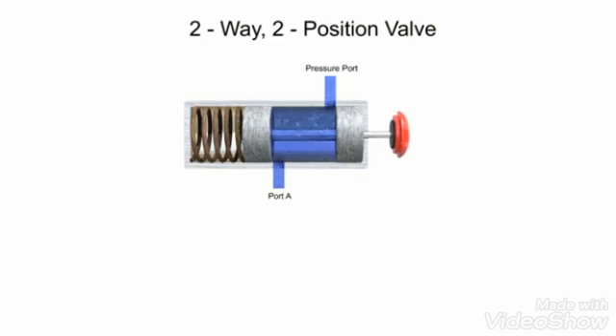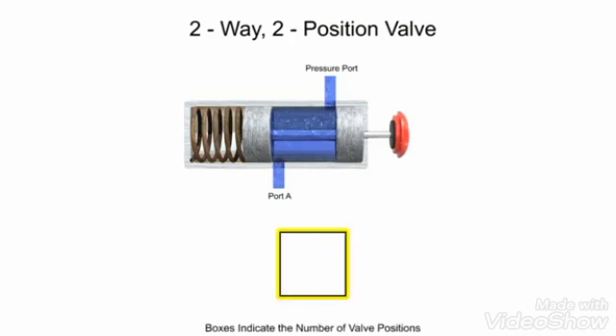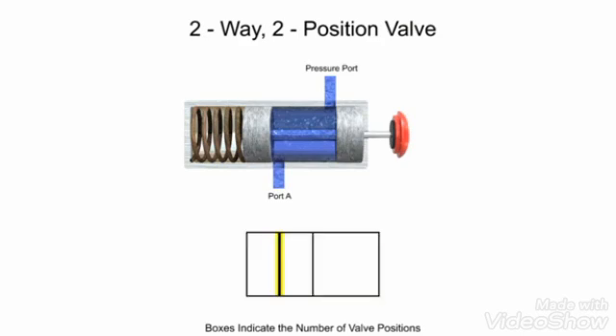To simplify fluid system drawings and schematics, all valves can be represented graphically. Boxes, sometimes called envelopes, are used to indicate the number of valve positions and functions. Since this is a two-position valve, its graphic representation has two adjacent boxes. Continuous lines are used to indicate fluid flow between ports. For complex valves, the ports may also be labeled.